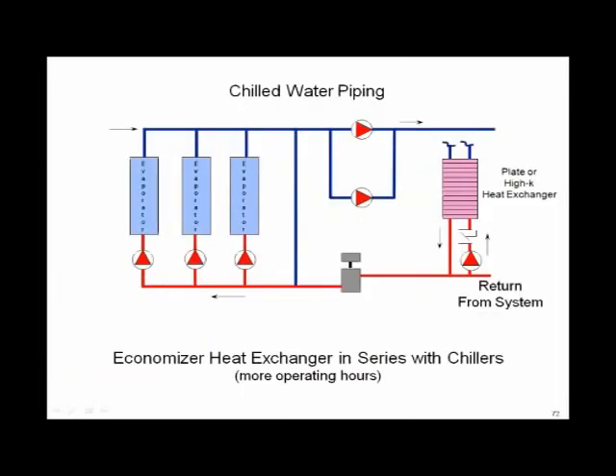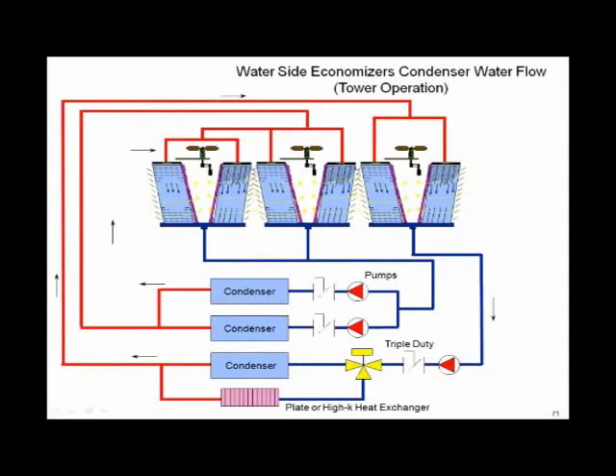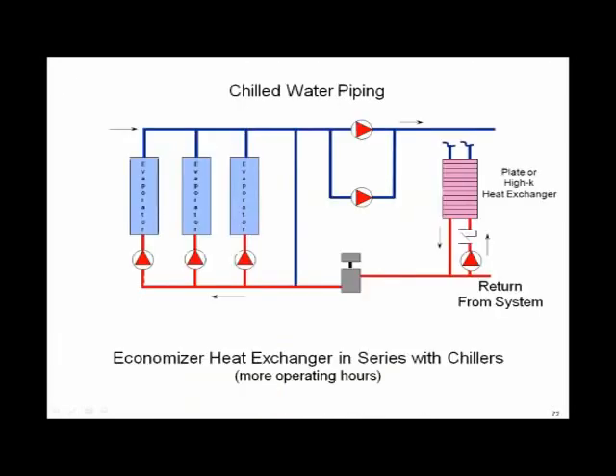So where do we put the waterside economizer to integrate? Now, in this slide, we're looking at the cooling tower side, the condenser water side, the 85, 95 degree side, the 15,000 BTUs per ton side. Now I'm going to switch over to the chill water side. On the chill water side, we're looking at the 12,000 BTUs per ton load, the 45, 55 degree side. In other words, the water side economizer interfaces between what? Between the condenser water and the chill water side. So we've got two sides to look at.